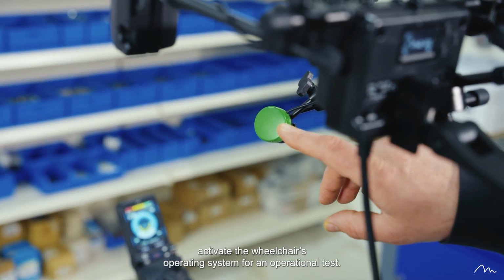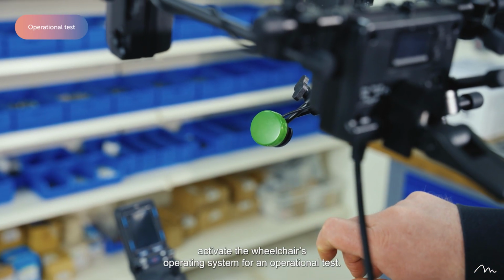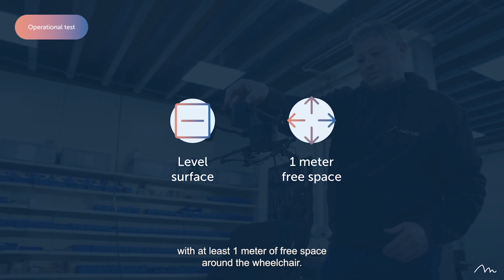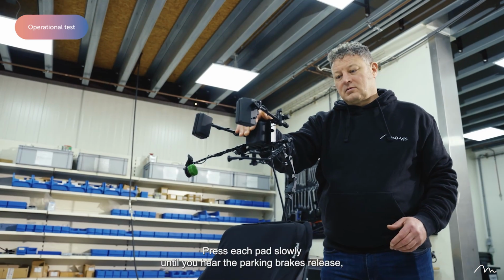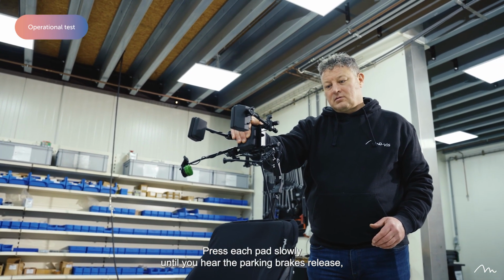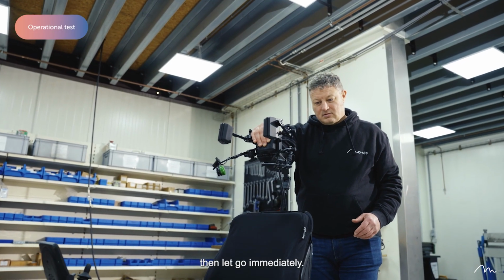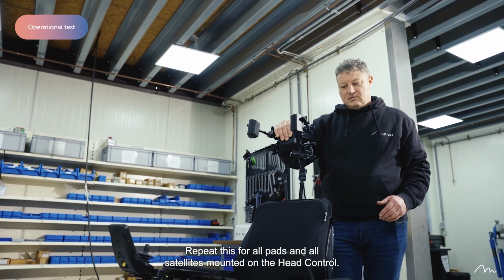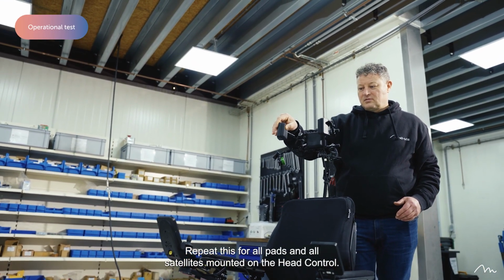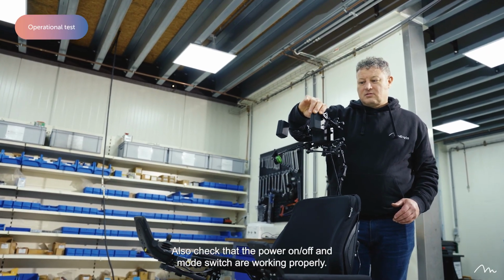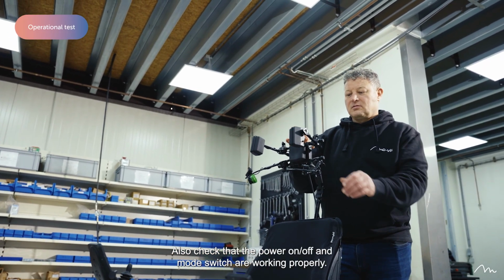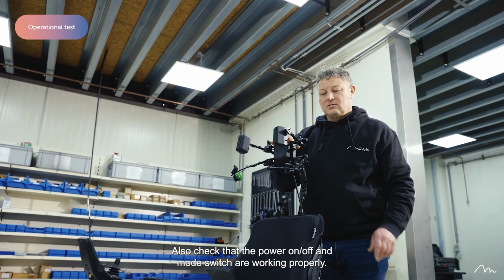Next, activate the wheelchair's operating system for an operational test. Make sure to do this only on a level surface, with at least 1 meter of free space around the wheelchair. Press each pad slowly until you hear the parking brakes release, then let go immediately. Repeat this for all pads and all satellites mounted on the head control. Also, check that the power, on, off, and mode switch are working properly.